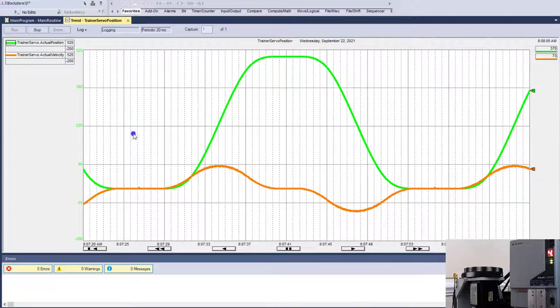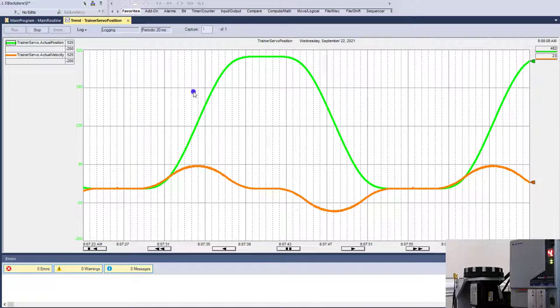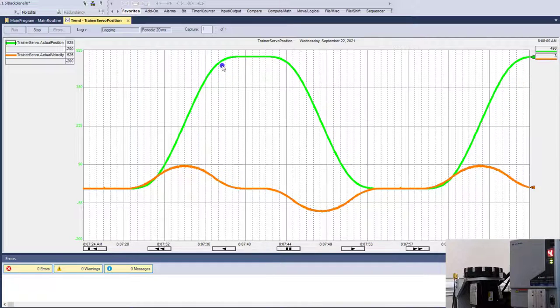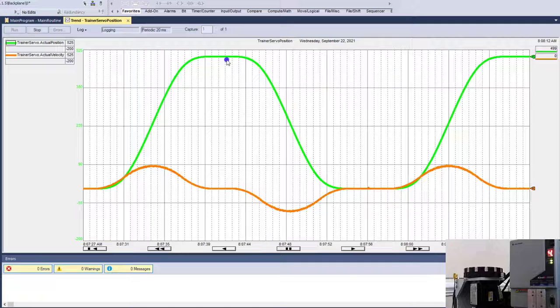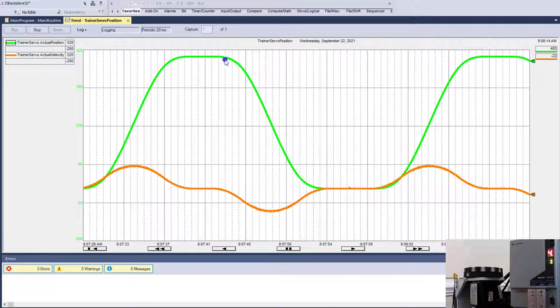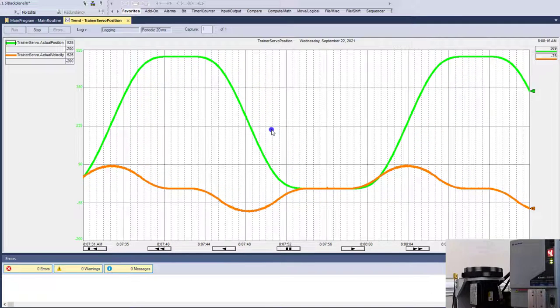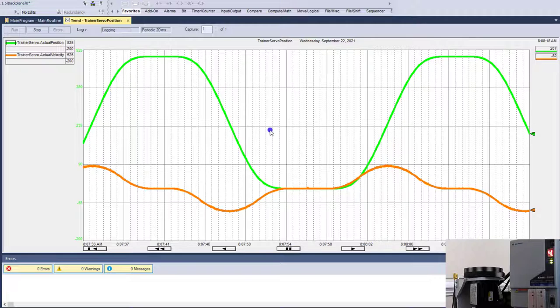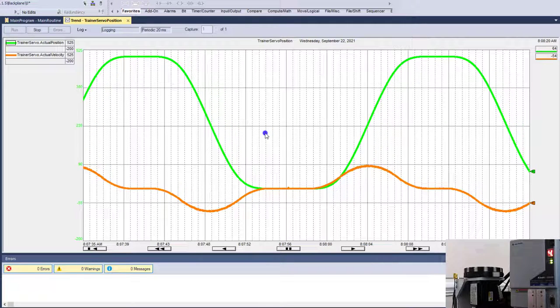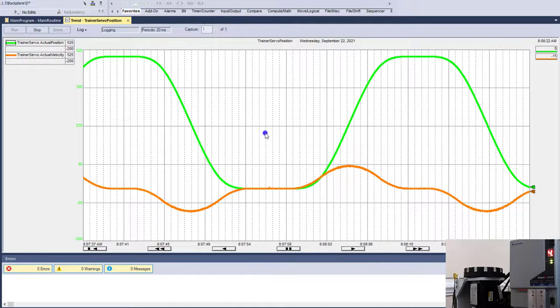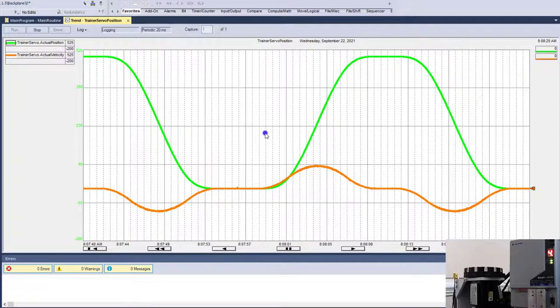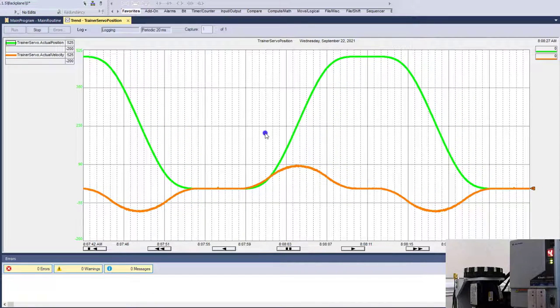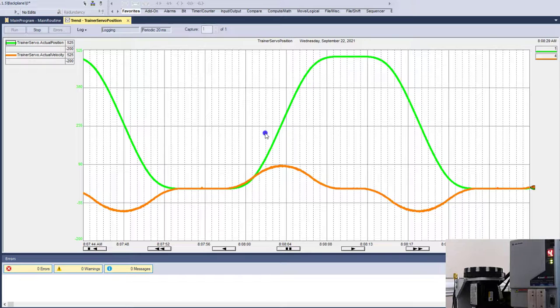As we move forward, you see a nice subtle move into its actual position and a subtle exit from its position. That's called an S-curve. Generally speaking, you use an S-curve for any kind of things that you would mechanically want to get less wear and tear on. Maybe something safety wise or maybe even something when it comes down to the machine has to be really, really precise.